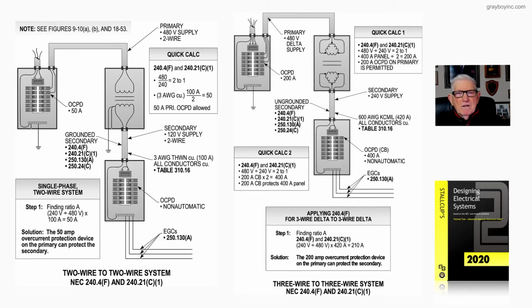So it is a grounded type transformer because we are grounding one side of that because it's single phase. We could take either side of that transformer, either L1 there or the other side, and ground it. Either side grounding would be okay. Now, notice in the quick calc, beginning with 240.4F along with 240.21C1, we have a 2-to-1 ratio. When we take the 480 volt primary and divide it by the 240 volt secondary, we get 2 to 1. So if we had, say, 100 amp on the secondary, we could divide by 2, and that'd give us 50 on the primary. Take 50 amps times 2, that's 100, and you'd come up with 100 amp there, see.